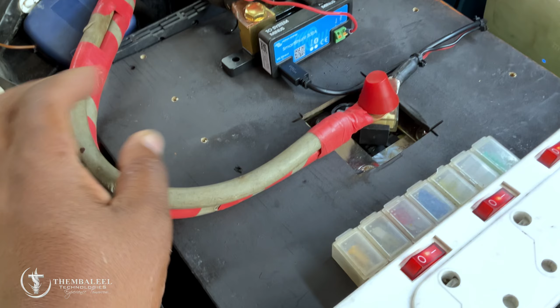So there are two 35 mil cables bonded together to create a 70 that goes through a circuit breaker. Now this circuit breaker is labeled 250 amps, and that's a lie. I bought these fake breakers, I don't remember when, and tested each and every one of them. I had a 300, I had a 400.